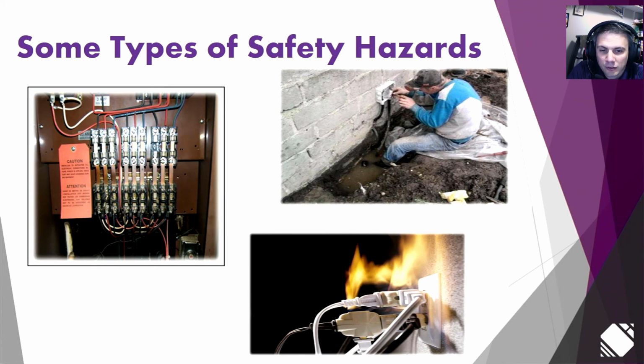But if you're plugging just on the borderline of what's acceptable on that breaker, and the breakers take time to operate, so if you can push it just into its overload condition and pull it back and cycle it, you can get it to a point over time - I'm not talking about instantly, but over a significant period - where that's going to cause heating on the cables and burn things out. That's why it's never recommended to put this many devices hanging. The other thing you can see is there's exposed copper, exposed plugs. If you needed to put this many plugs in, this is not the safe way to do it, let alone the heating itself.